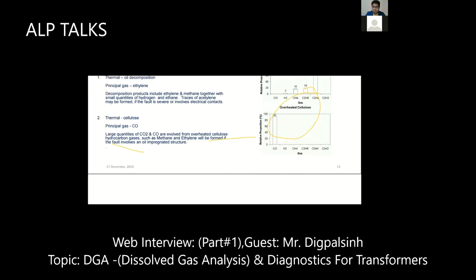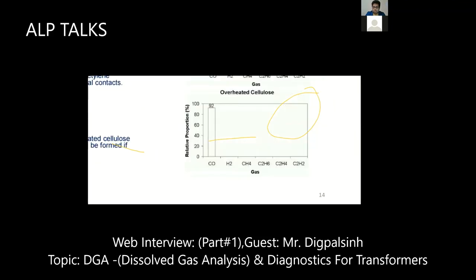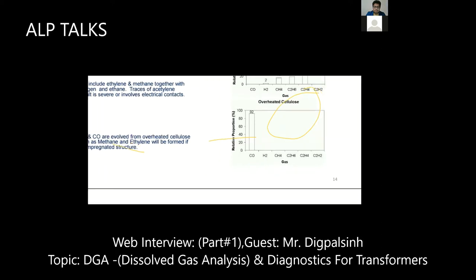You can find carbon monoxide with carbon dioxide. In that graph it is not shown, but CO and CO2 will be there, with some amount of methane and ethylene. Methane and ethylene will always be there if it is a thermal fault, but it depends on the amount of the gases, the ppm level of the gases.